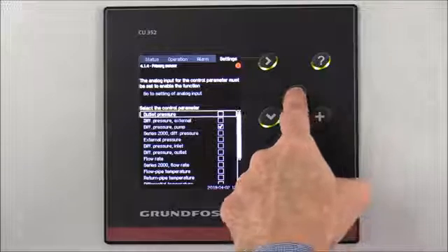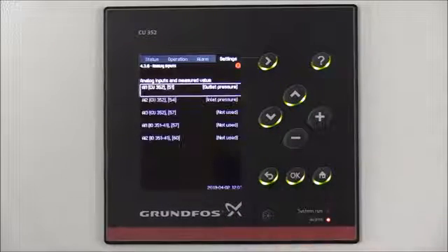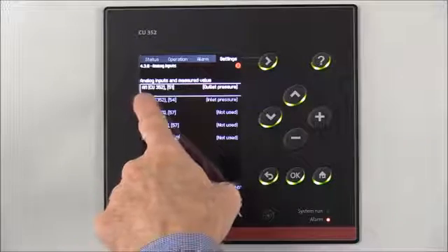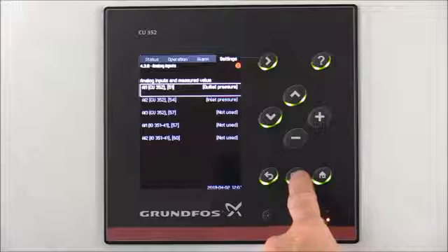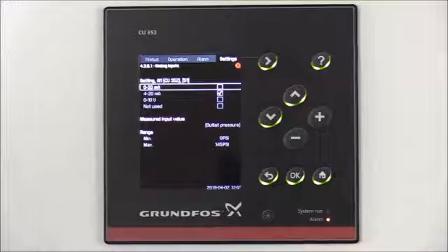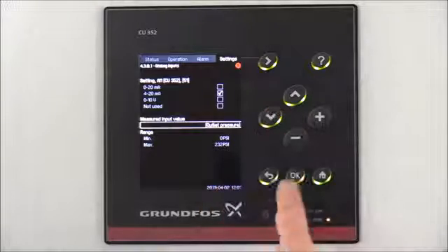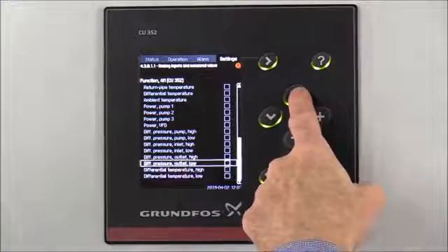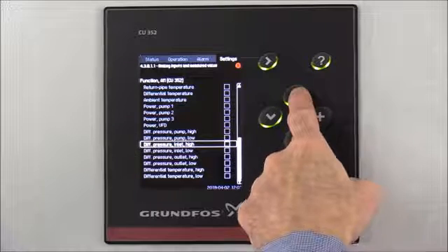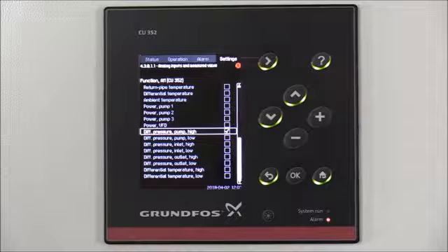We're going to arrow up to go to the Settings of Analog Input and select OK. First, we're going to change the settings for Analog Input 1, which is currently set on Outlet Pressure. We'll press the OK button and arrow down to Measured Input Value. Press the OK button and arrow to Differential Pressure Pump High. Press OK to select that option.